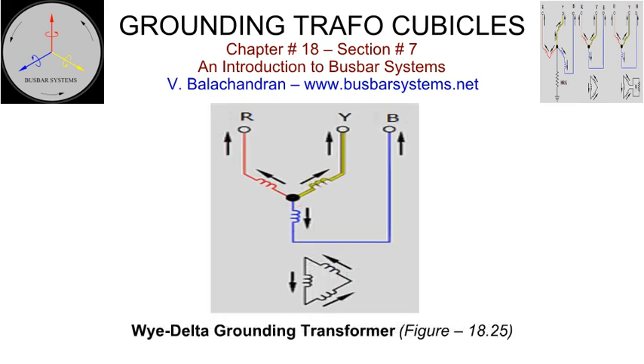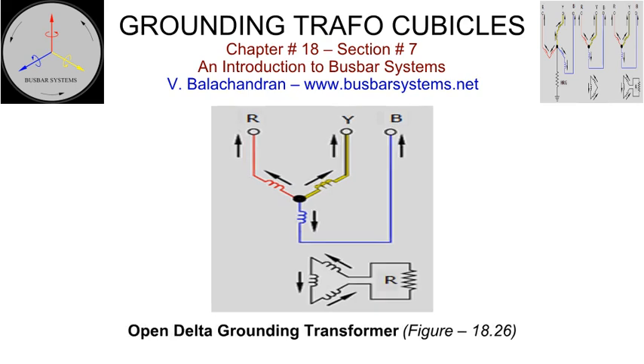Y-delta grounding transformer. Single-phase transformers with shell-type construction can be installed in individual compartments of the surge protection voltage transformer cubicle when separately installed. The line terminal of the primary winding is connected to the tap-off bus and the neutral terminal is connected to the earth in each of the cubicles. The low-voltage windings are externally connected to form a closed delta connection to provide path for the zero-sequence current to flow. The sizing of the transformer can be carried out to provide the reactive volt-amperes of the capacitance to the ungrounded path.